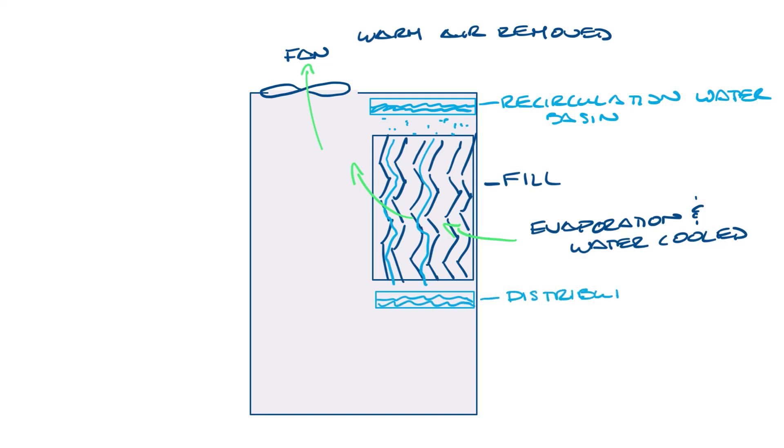Air is drawn in through it and evaporation happens and the water is cooled and the warm air is removed. Then the water goes to a distribution basin. Below that is the coil. So the hot process fluid is going through the coil and as recirculation water is distributed over the coil, it cools the process fluid.